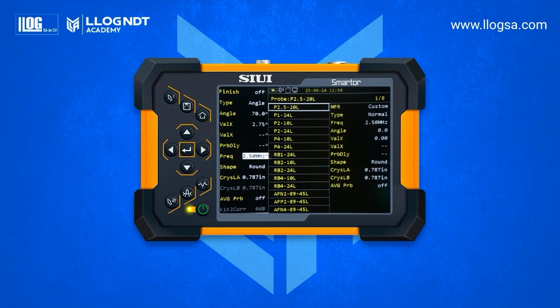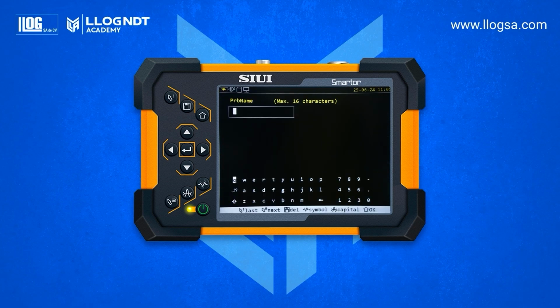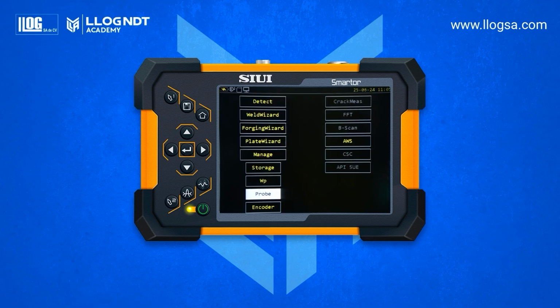Next, select the frequency, 2.25 MHz. Choose the shape of the transducer, round or rectangular. Then adjust the size of the crystal contact area, 0.625 by 0.625 inches. Save the transducer configuration and assign it a name. For example, AWS 2.25. Press the Home key to finish. And finally return to the detection menu.